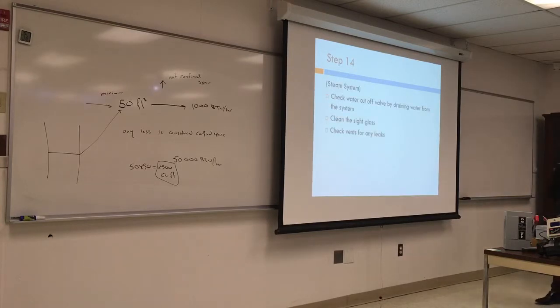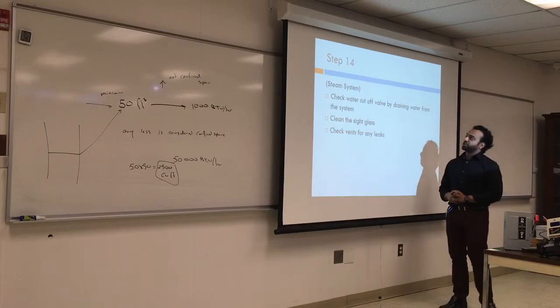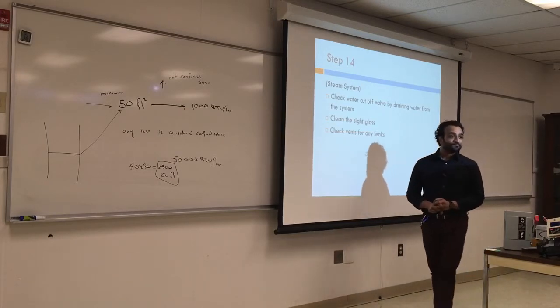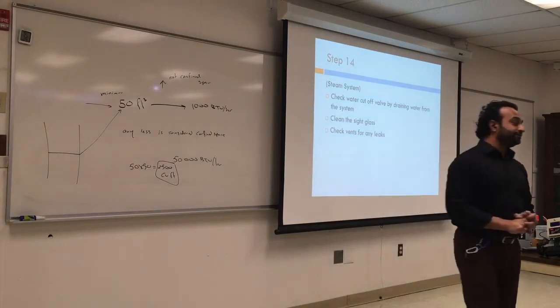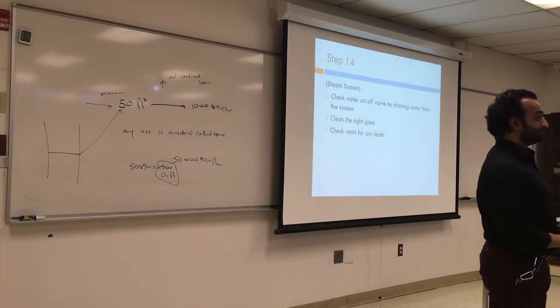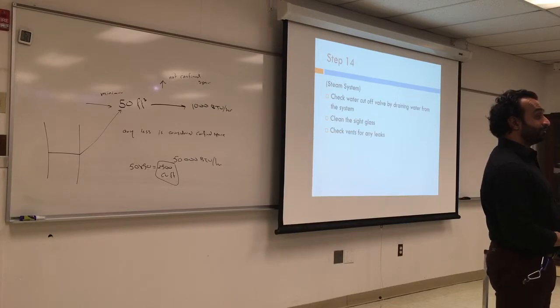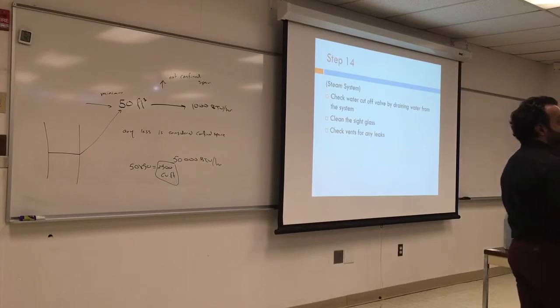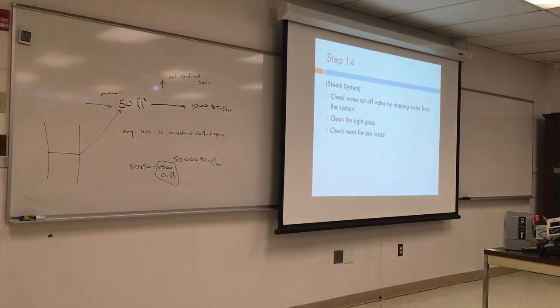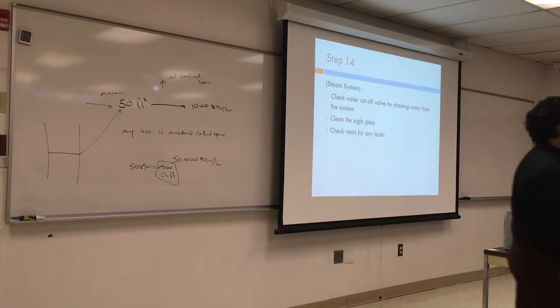For steam, the most important thing is to check the low water cutoff. How do we check for low water cutoff? Wait till it drops. You gotta turn it on and drain the system, and make sure it cuts off. That is very, very essential. Most of the issues with steam systems come because the low water cutoff is not activated. And the low water cutoff can go bad because it's electronic. So turn the system on and drain the water slowly and see if it drops below the level, and make sure that it does cut out the system.